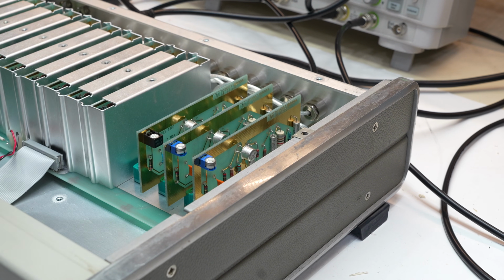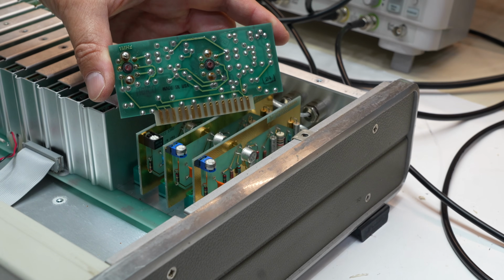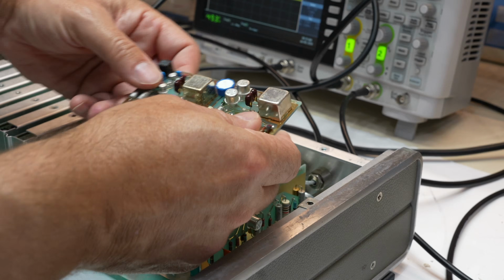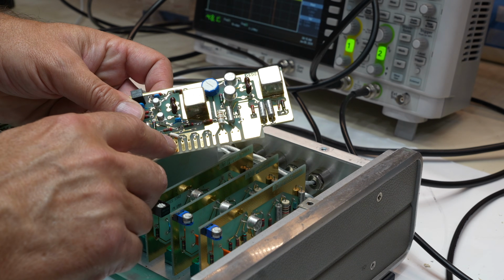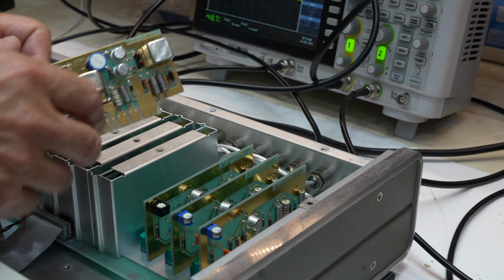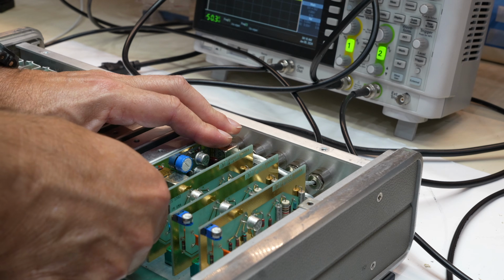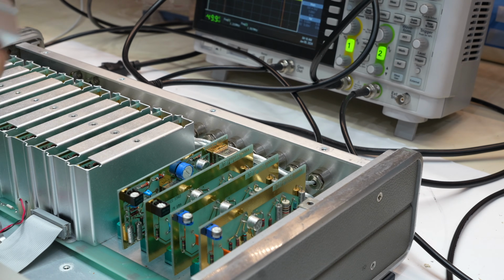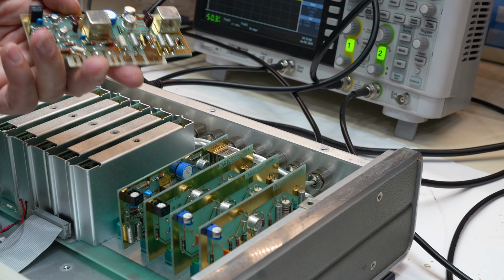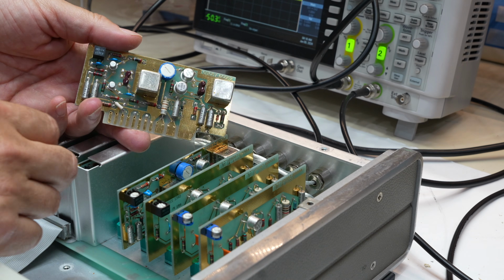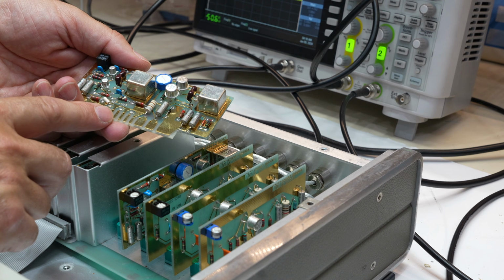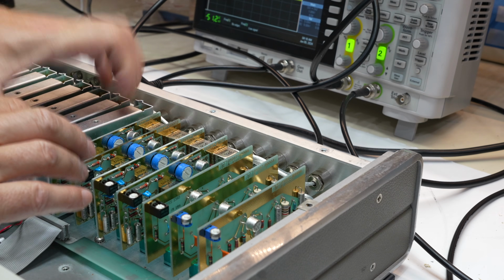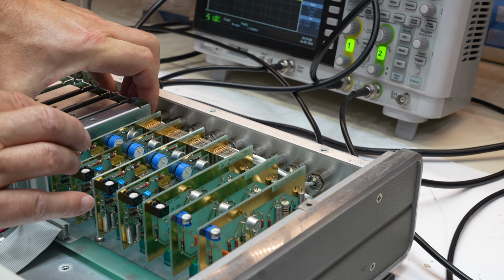And if I can take it out, this is indeed a 1 megahertz, and it's picking up the output of the A card, bus A. I'm going to check them all that they are properly configured. I think since this is a factory configuration, it should be fine. Yes, this is on A. So 4 cards properly configured at 1 megahertz.